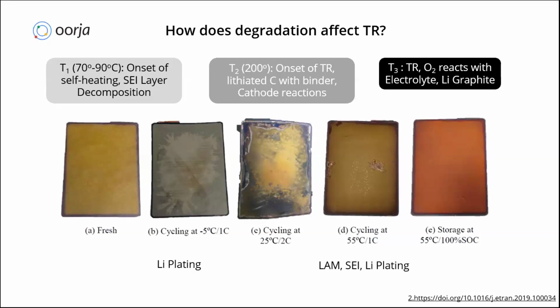As the cell ages, whether through 300, 500, or 1000 cycles, and so on, the T1 and T2 temperatures start coming down. Because of that, a cell that could earlier withstand up to 90 degrees Celsius thermal load may now only withstand 70 degrees before self-heating reactions start. This means the cell becomes more susceptible to thermal runaway as it ages. How much it gets affected depends on how the cell is used, how it ages, and what dominant degradation mechanisms are present based on usage.